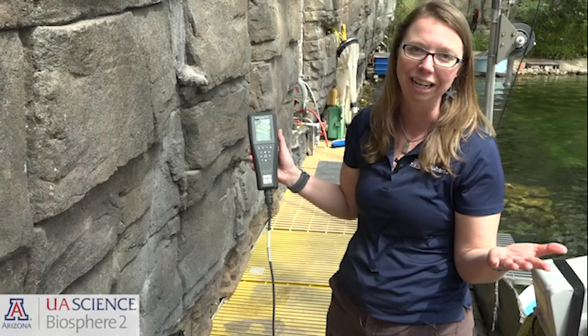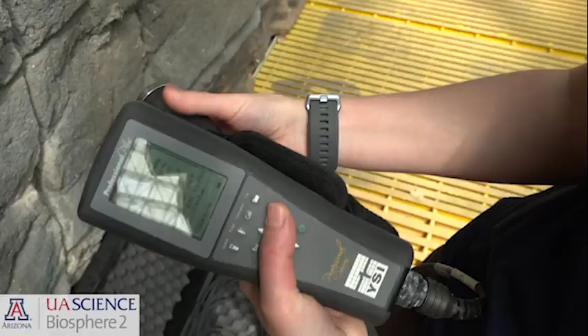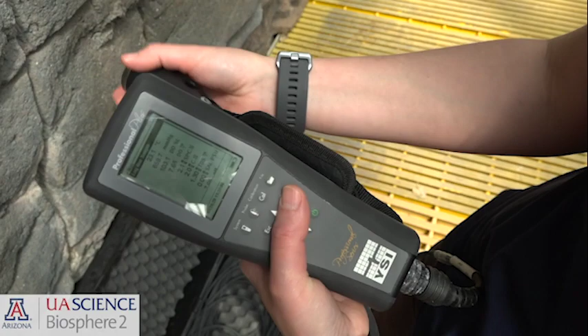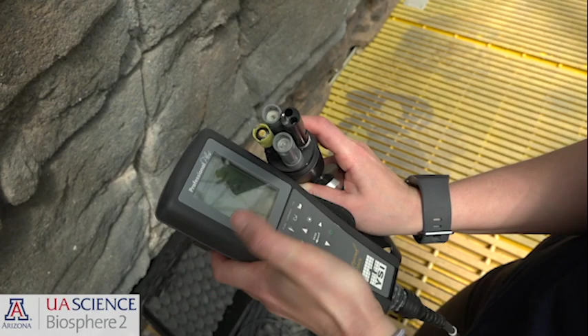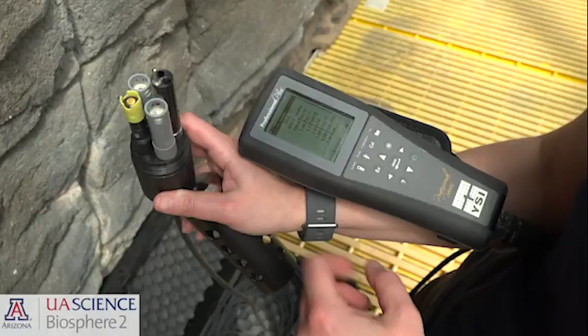The first is called a YSI. It's the company, it's like the Kleenex brand of sondes. This device can be set up to measure a number of different physiochemical parameters, so physical and chemical parameters, at depth on the particular system of interest. I'll open up this casing that's used to protect the sensors and show you those 4 sensors. This is the temperature and conductivity sensor, dissolved oxygen, pH, and ORP, which measures the redox potential, so the ability of the water to oxidize or reduce chemicals.